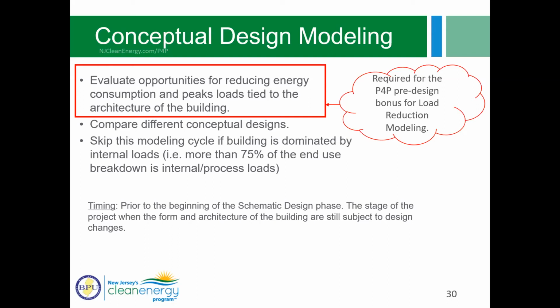So there's a note in ASHRAE 209 that this cycle can be skipped if the building is dominated by internal loads. So let's say you had a process production facility or something related to industrial process. It wouldn't be a cost-effective use of the modeling effort to spend time looking at the architecture of the building because it's dominated by process loads, not HVAC. So this is conducted prior to the beginning of the schematic design phase. Of course, you want to do this before the form and architecture of the building has been set, so this needs to be done where those design parameters are still subject to change.